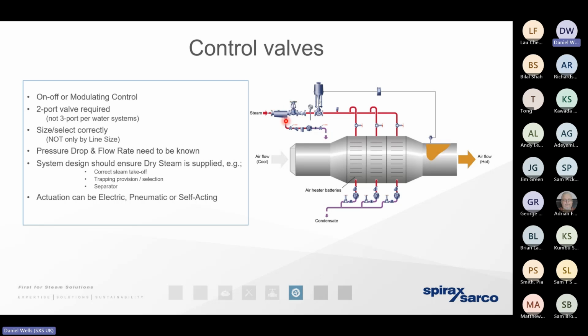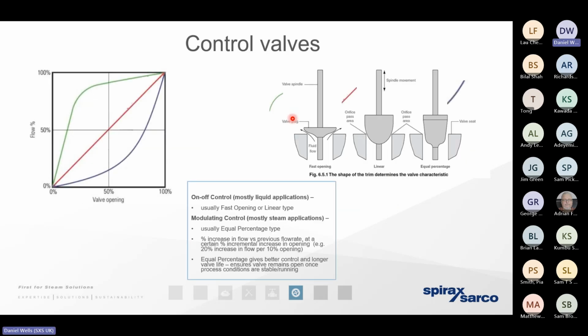Also, we want to ensure that we've got those ancillaries. We need to make sure that we're removing the moisture to keep the steam as dry as we possibly can. And it stands to reason that if we're using a control valve on steam, it needs to be a control valve that is specifically for steam. A lot of water-based control valves are what we call fast opening valves. And if we've got a fast opening valve, because it's going to operate very, very close to its seat for the vast majority of its operational life, it means that it would be far, far more susceptible to erosion and failure than a specifically designed steam control valve with an equal percentage characteristic.